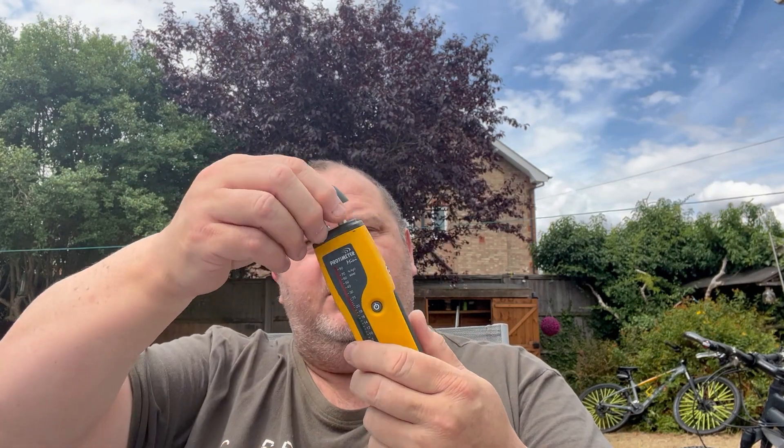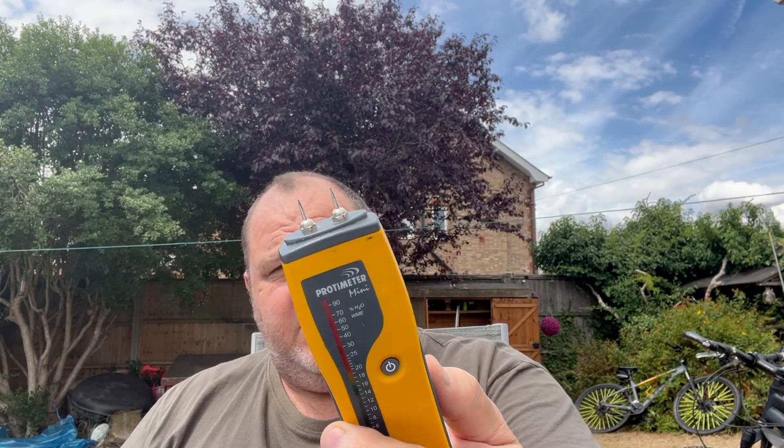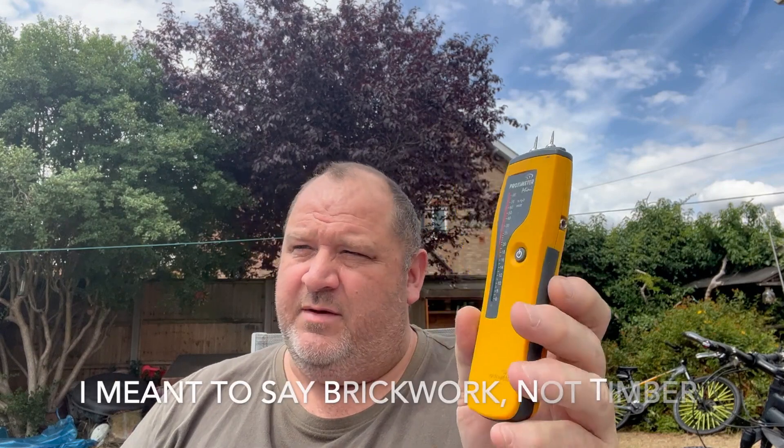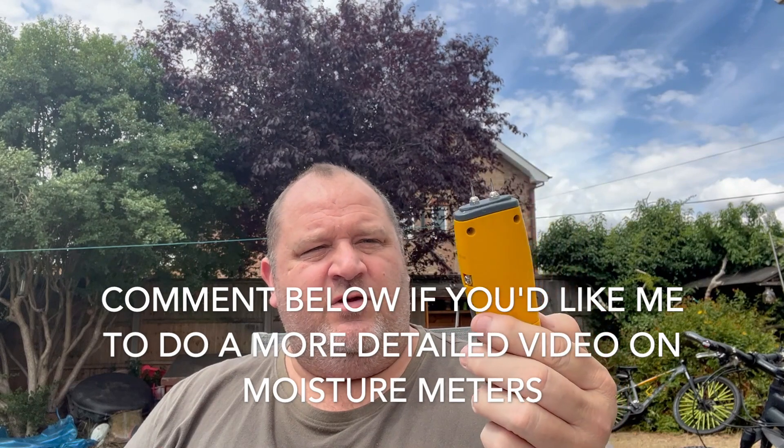I'll start with the simple one — the Protimeter Mini. All it has is two prongs, so it's a contact probe. It measures in WME, which is Wood Moisture Equivalent, so it's only intended for use on wood. However it can be used on brickwork, plaster, stuff like that, but with the caveat that you may get a false positive using this — but you'll never get a false negative. I'm not going to go too much into these; maybe I'll do a video on how to use these properly in a later video.